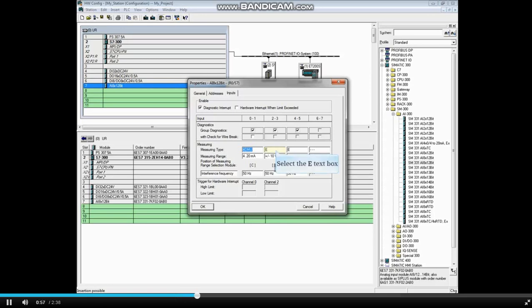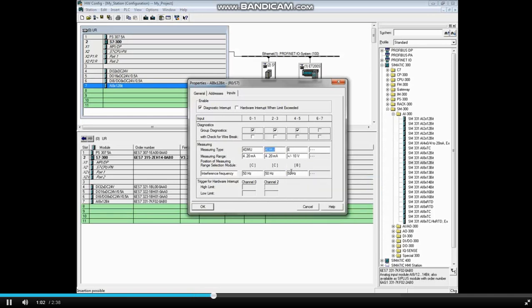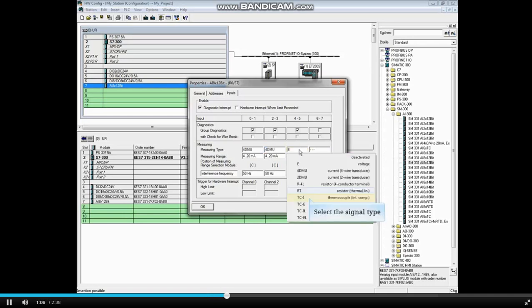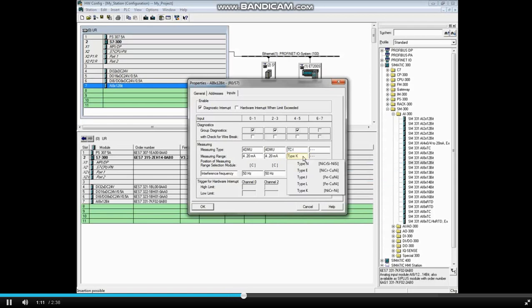You will need to choose the measuring type for each channel group. For channels 4 and 5, the measuring type will be thermocouple. The measuring range will be type K.